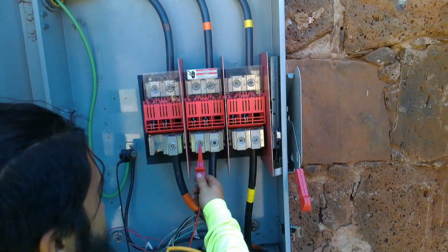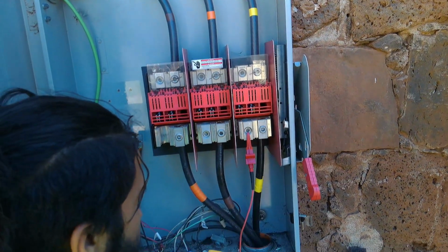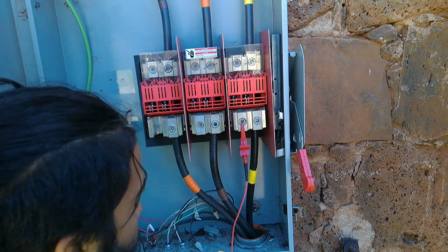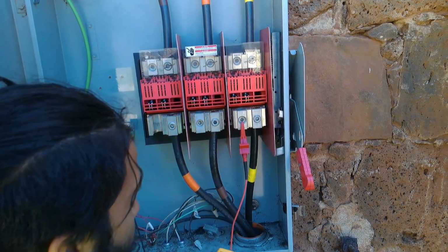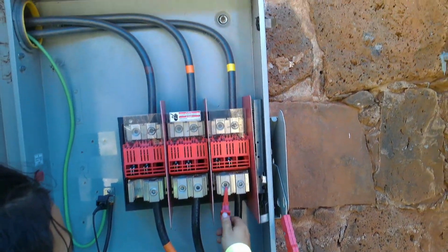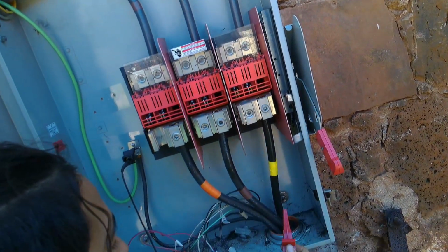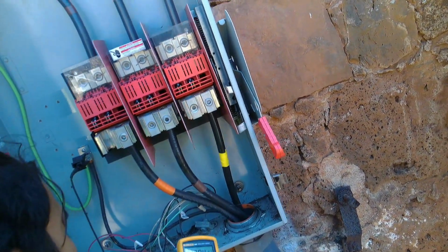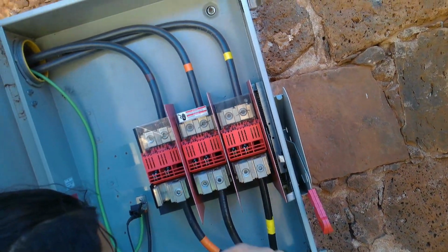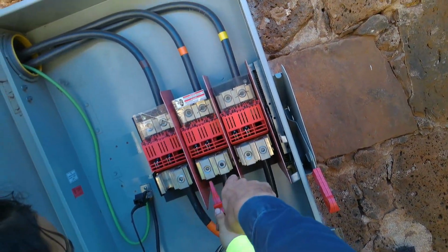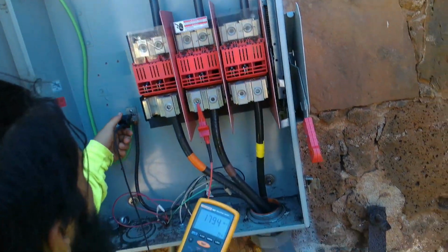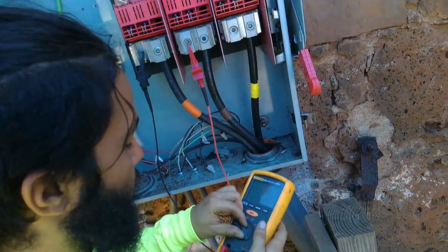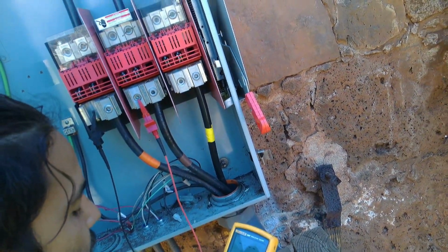And then do line 3. Good. Okay, now you're going to switch this red over to the ohms. And then you're going to put your clip on 2, red on 2, and black on 1. And we're checking the winding resistance now. But we're not going to put 1000 volts through. We're just going to put it in old-fashioned continuity check, and just hold down test.